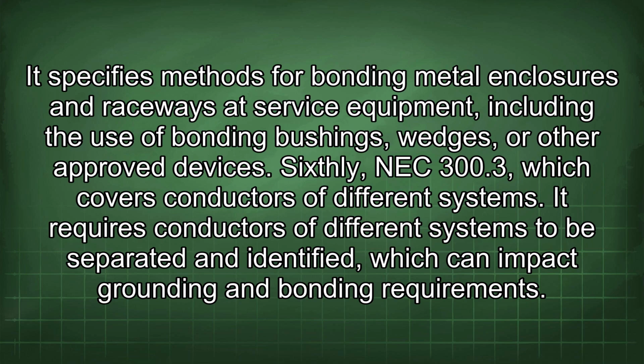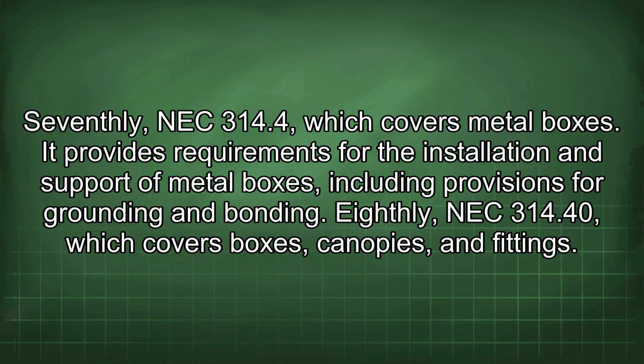Sixthly, NEC 300.3, which covers conductors of different systems. It requires conductors of different systems to be separated and identified, which can impact grounding and bonding requirements. Seventhly, NEC 314.4, which covers metal boxes. It provides requirements for the installation and support of metal boxes, including provisions for grounding and bonding.